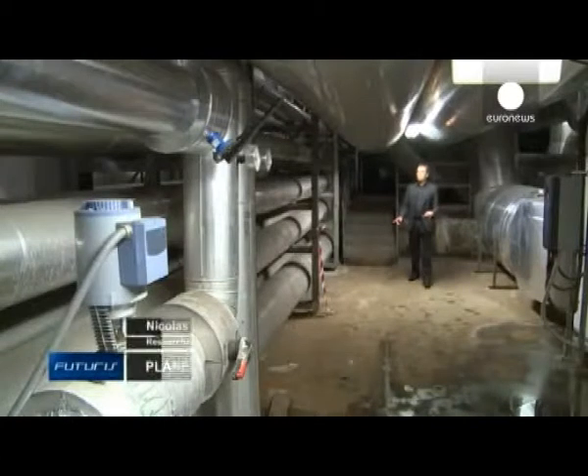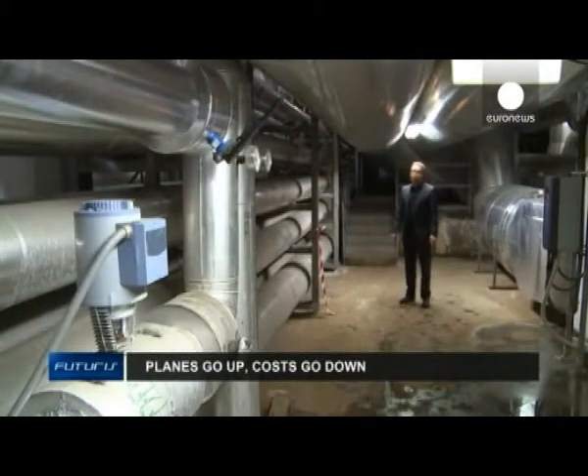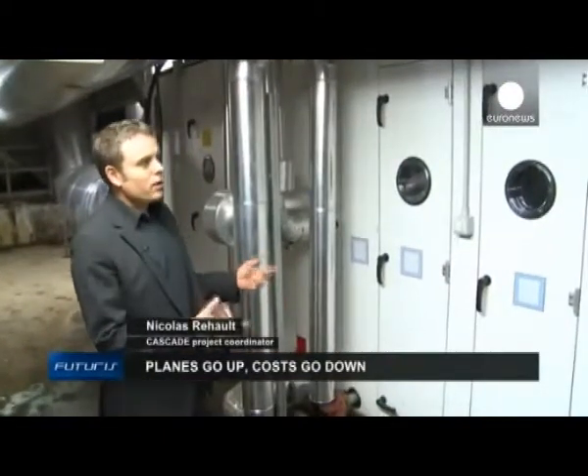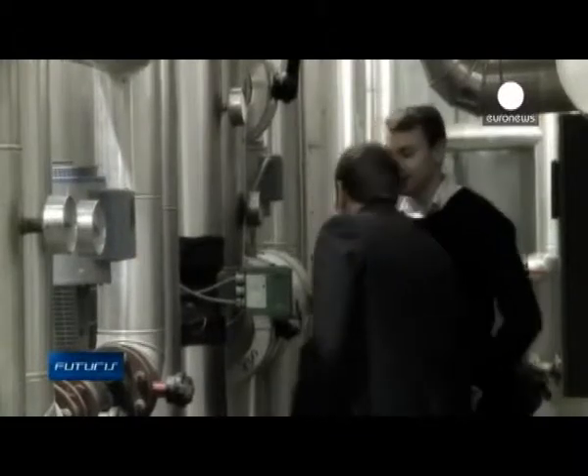We're right under Terminal 1 at Fiumicino Airport, and through all these kilometres of pipes, air is pumped into the terminal building. And here is an air handling unit. Units like this use a lot of thermo and electric energy. All across the underground ventilation network, researchers have installed sensors that automatically detect various hidden problems causing waste of energy, such as simultaneous heating and cooling or mechanical malfunctions.